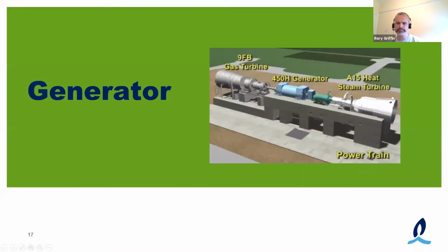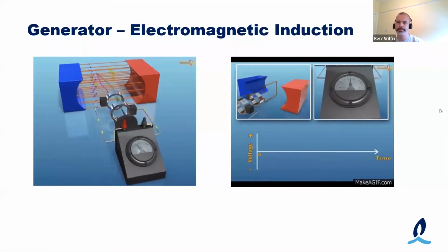So I found a GIF which kind of helps explain this a little bit better. So I suppose, look, electromagnetic induction is the process in which a conductor, if you put it in a particular position, whether it's rotating or it's stationary, but there's a magnetic field around it that's rotating, you'll induce currents in the coils. So that's kind of what's happening here. In this example here, you can see the carbon brushes on the slip rings. So this is how the current is being transmitted in. As I mentioned for Whitegate, it's a little bit back to front in that the magnet is the rotating part and the coils where you're inducing the current is the stationary part, the stator winding.